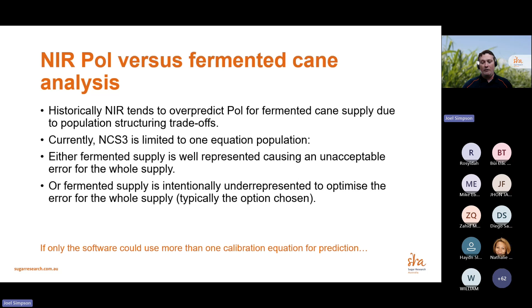What would be nice is to have more than one calibration, one for healthy cane and one for different levels of fermented cane. If only we had a way to do that, because at the moment our current software can only do one calibration suite at a time. So that brought us to developing the multiple calibration method. Here we have a scan, and the first thing that happens is it hits a classification equation. We apply a classification equation to determine which of three groups it is in: juice, beer, or wine. So unfermented, partly fermented, or very fermented cane supply.